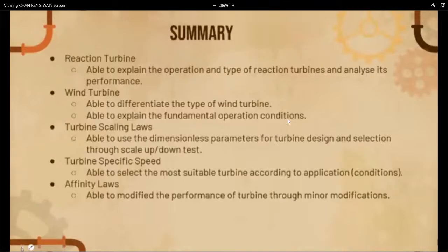And the affinity law actually is the same as the pump affinity laws, applicable for both pump and turbine. So with the affinity law, you should be able to find out what is the performance of the turbine with some minor modifications, for example, the change of the diameter or the change of the rotational speed.